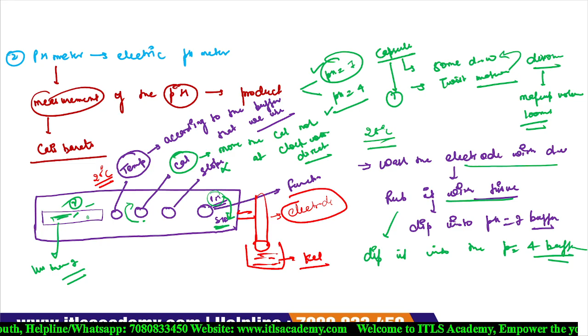Now at that time, you don't touch the temperature knob and call knob. You just move the slope. When you move the slope in a clockwise direction, then the value decreases and reaches 4. When it reaches 4, your pH meter is calibrated. Now again, you move that function knob from the pH to the standby, and you have to wash your electrode with the help of distilled water and rub it with the tissue paper, and then again dip it into the sample. So how you calibrate the pH meter is clear.